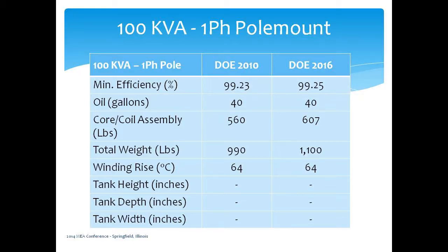On the 100 kVA pole mount, I want to touch base on that one real quickly too, because you can see that's only a 0.02% difference, yet it still made a fairly significant impact on the core coil assembly size, and with a similar winding rise, so you'll see a little bit larger increase in weight. You're going over 1,000 pounds with these things at 100 kVA.